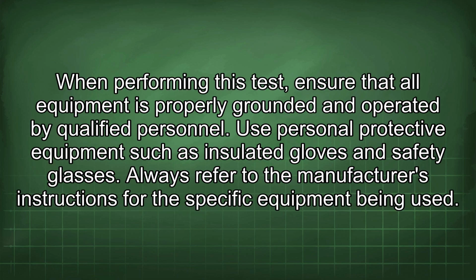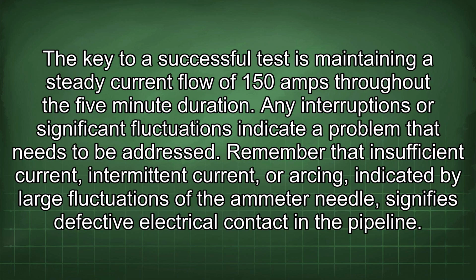When performing this test, ensure that all equipment is properly grounded and operated by qualified personnel. Use personal protective equipment such as insulated gloves and safety glasses. Always refer to the manufacturer's instructions for the specific equipment being used. The key to a successful test is maintaining a steady current flow of 150 amps throughout the 5-minute duration. Any interruptions or significant fluctuations indicate a problem that needs to be addressed.